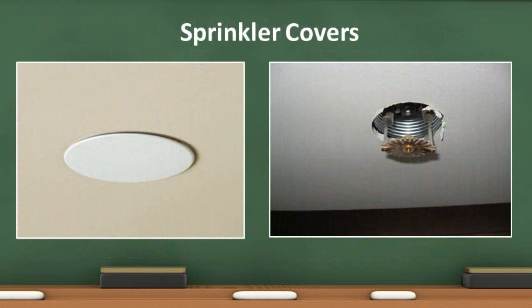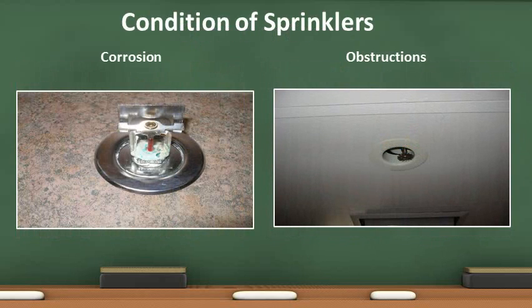Covers for recessed sprinkler heads will release and allow the sprinkler head to drop out at a certain temperature. The deflector will drop down and water will disperse over the protected area. Covers should be replaced when missing or painted. In the photo on the right, the sprinkler cover is missing and will need to be replaced. The sprinkler head in the photo on the left is corroded and this will cause it to malfunction. The bent and obstructed sprinkler head on the right will not protect the area being covered.